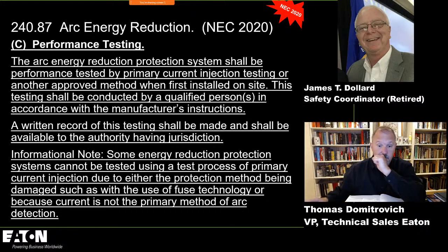Absolutely. Another big change in 240.87, it's not in C, C is new, is that we required that you install a means of arc energy reduction, but we never required that you document that it would actually work. Yeah. And in 2020, that is a requirement. Yeah. I mean, you have to prove that the method you chose is going to work within the amount of arcing current that exists. Yeah.